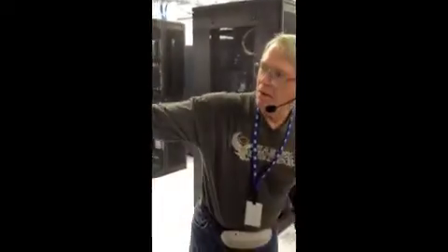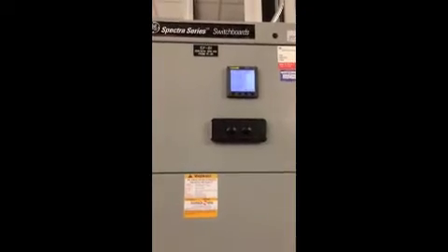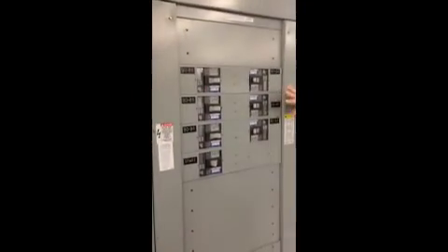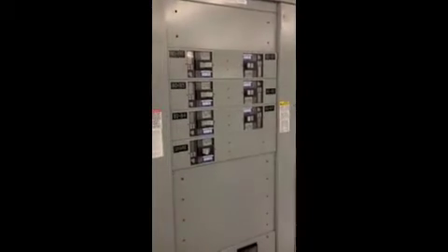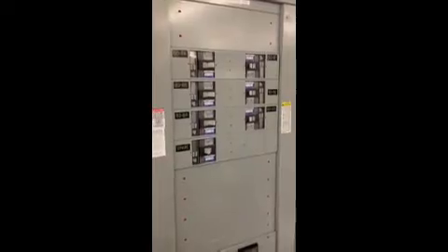Okay, and then here next to me is part of the electrical infrastructure. Power is fed to the data center at 480 volts, three-phase. Goes into the transformer, which is a big blank box there, where it's transformed to 208 three-phase with a neutral, so we can supply 208 or 120 to any rack. And it's distributed through these panels here. Each of these feeds a single Starline bus rail, and that's 400 amps of power out to the bus rail. So with that, let's move on over here to the sandbox.